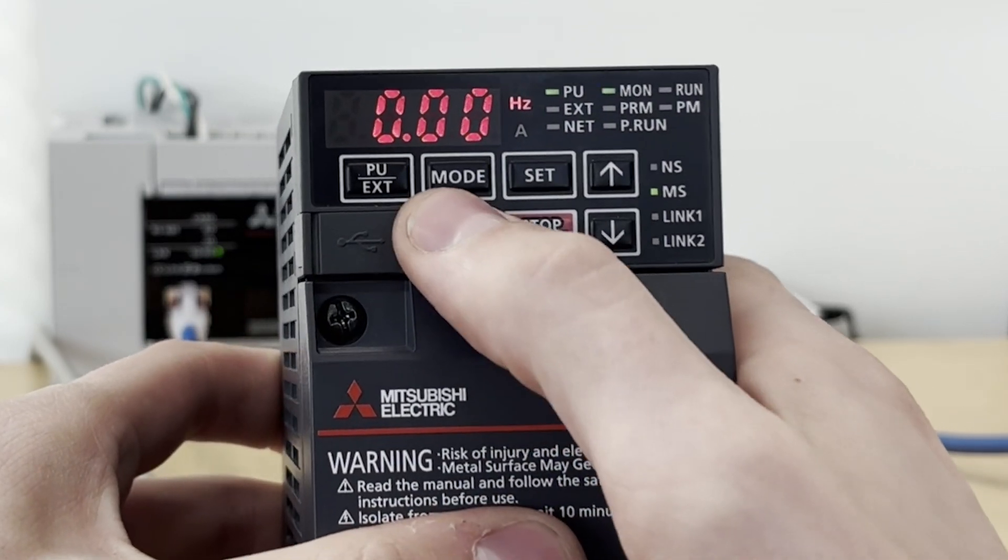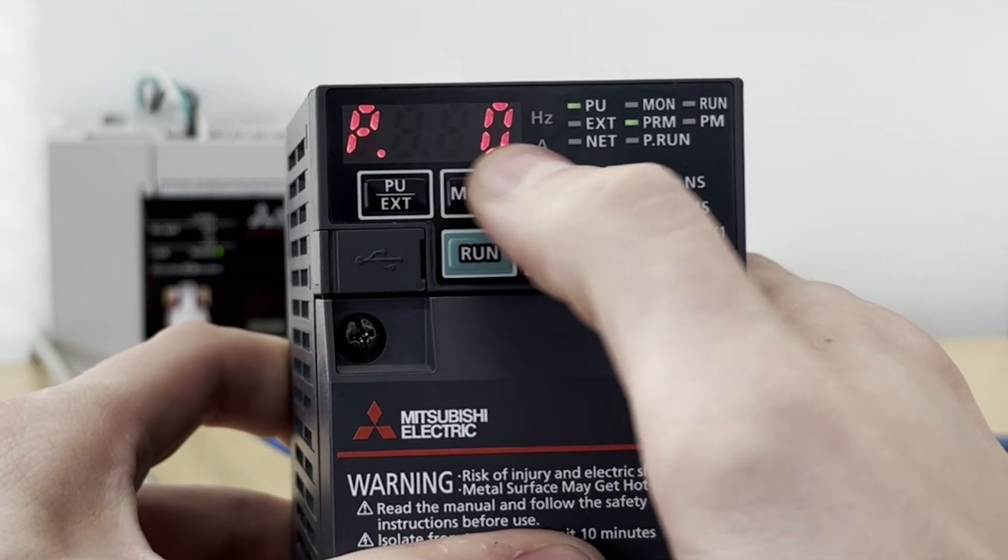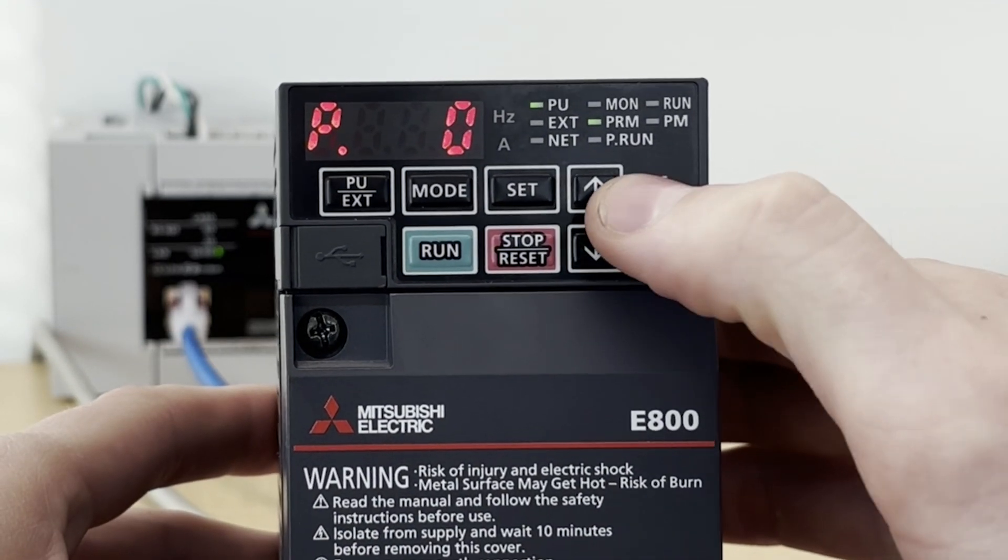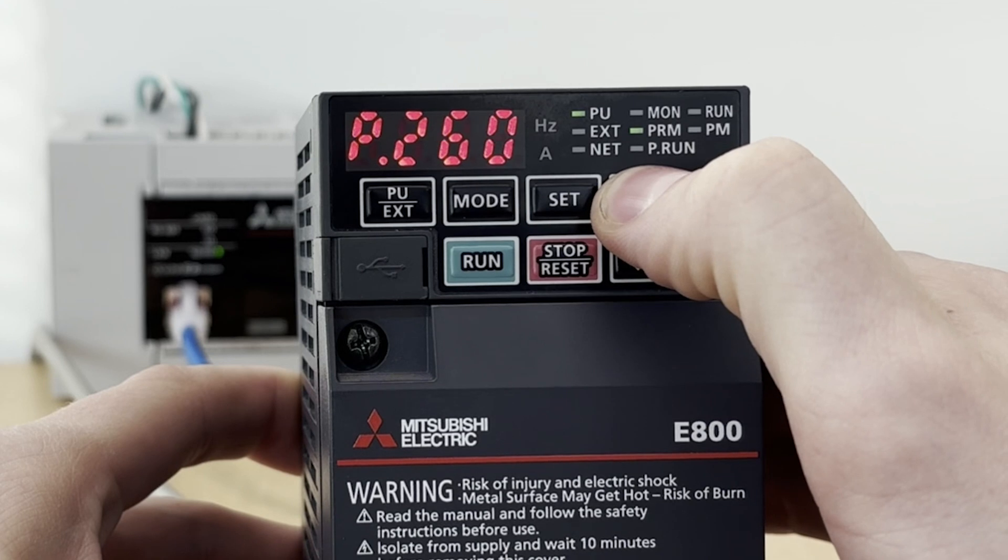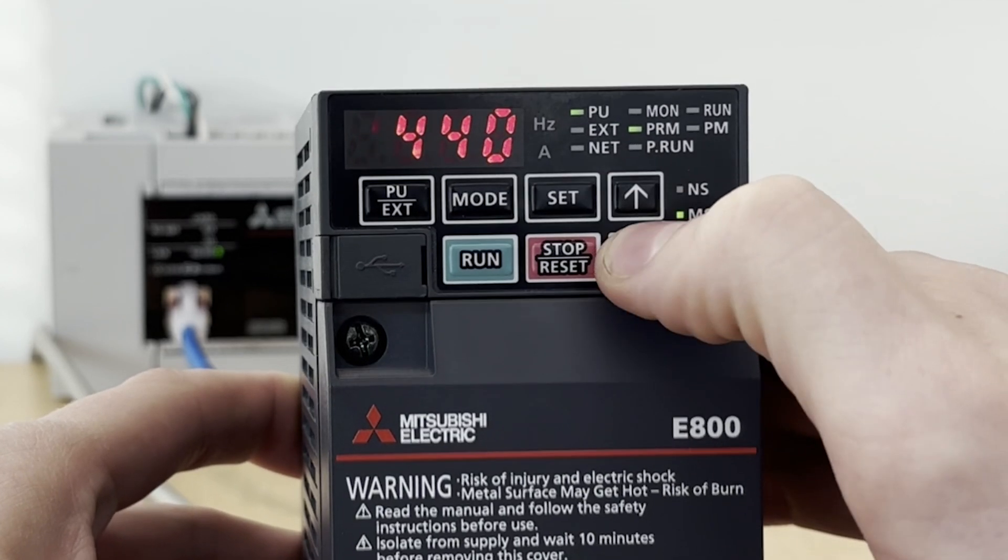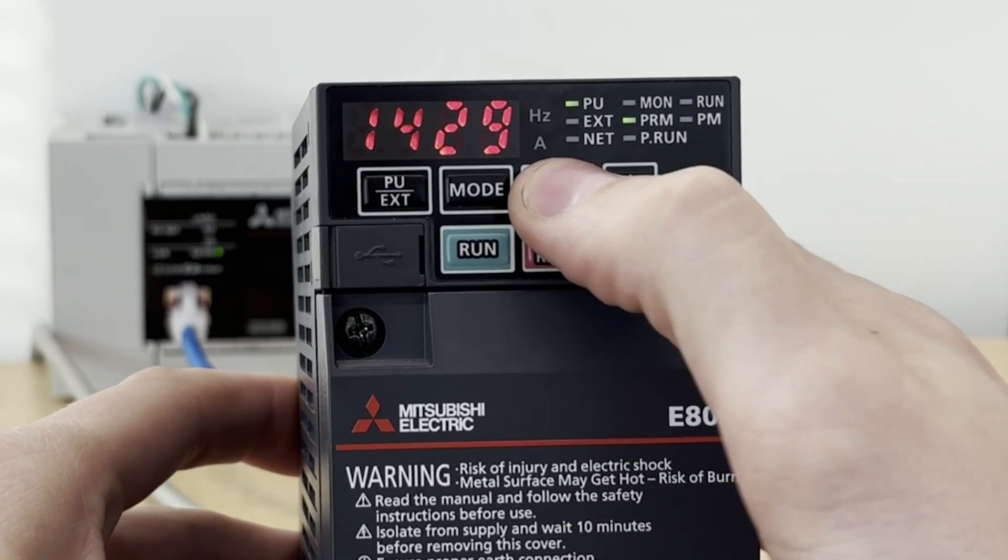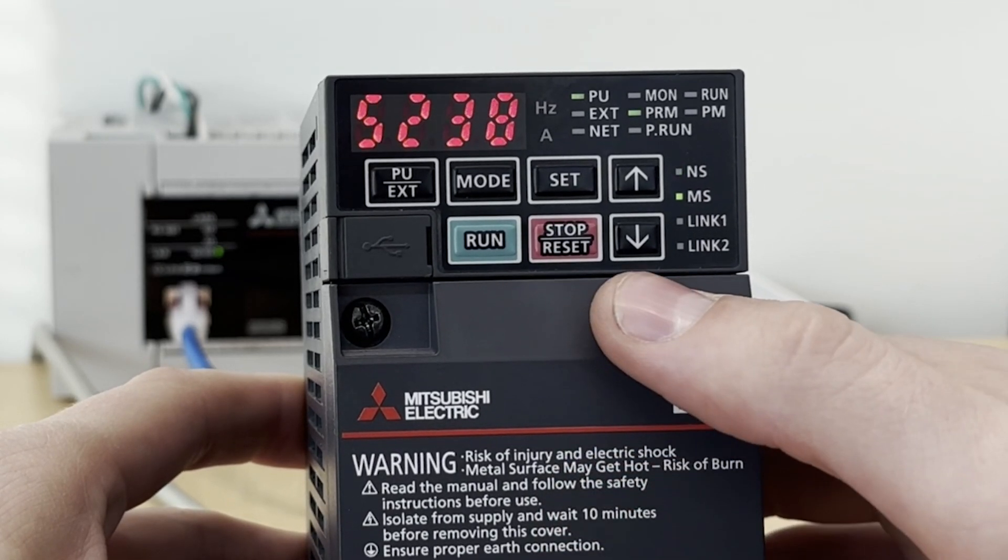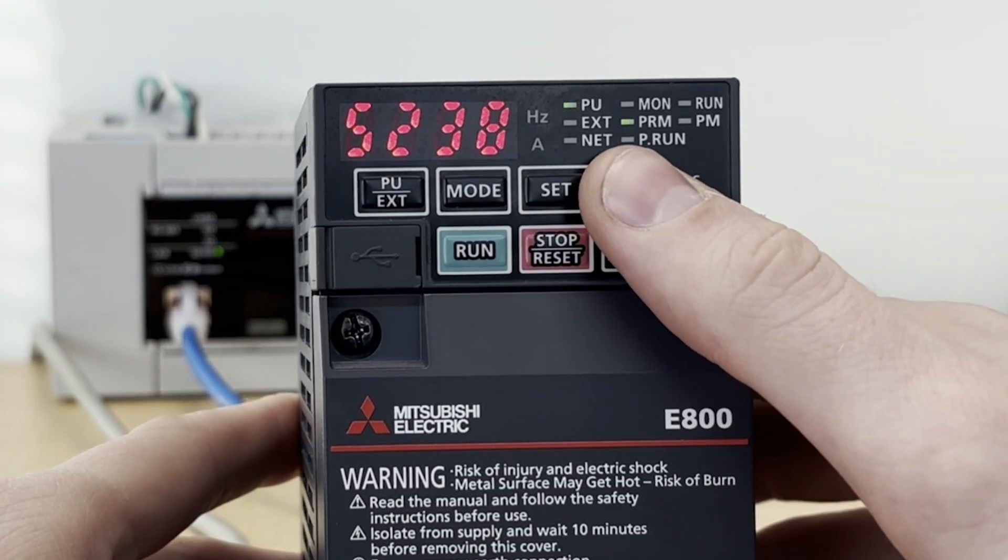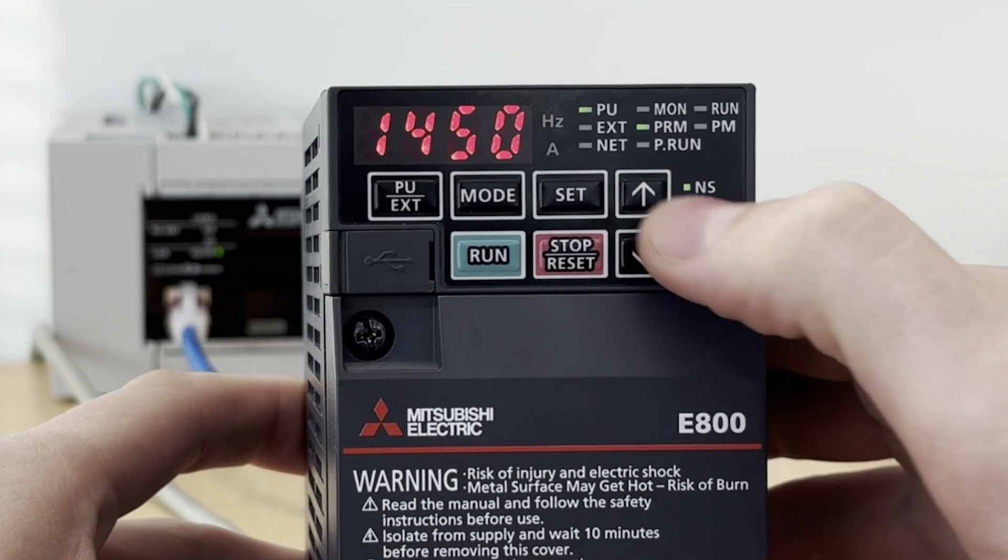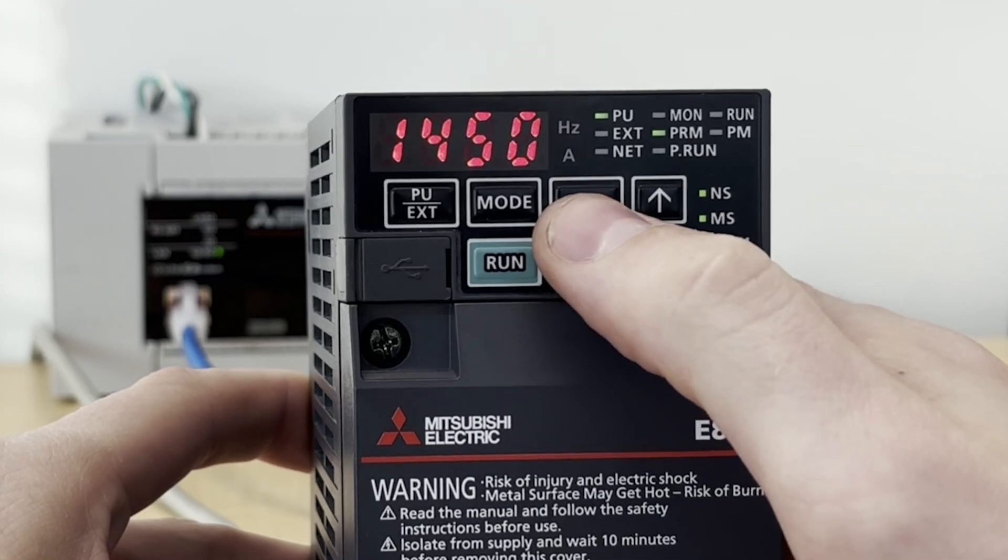To set the parameters, I'm going to press the mode button to get to the parameter set screen. The first parameter that we need to set is parameter 1429. So let's hold the up button until we get to 1429. This parameter sets the communication mode of the inverter. The default value is set to communicate over CC-Link IE TSN. We're going to need to change it to a different number to allow it to communicate over CC-Link IE Field Basic. The number that we want is 61450. Just hit the up button twice to get to 61450 and press set.